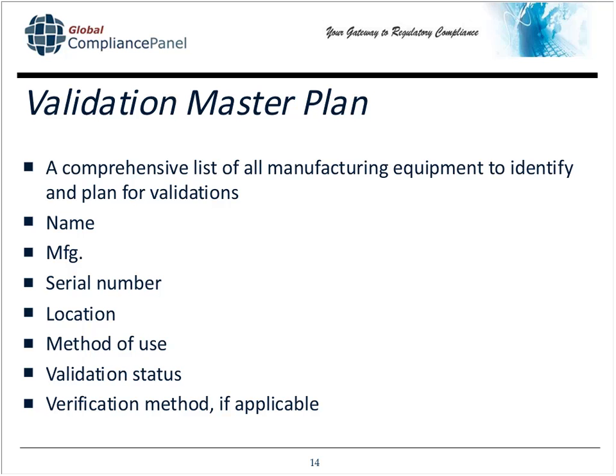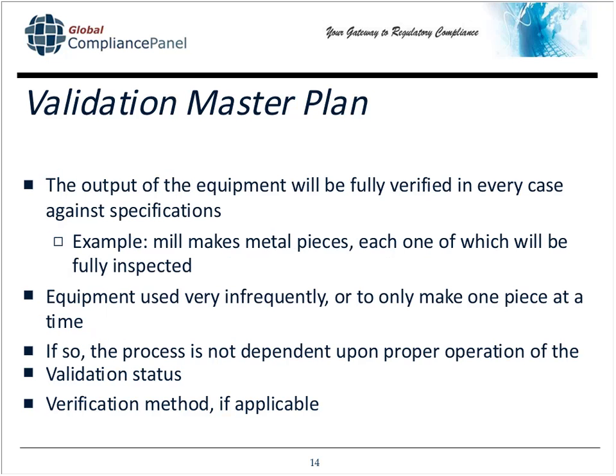In our validation master plan, what we have is a test reference number for the IQ, OQ, and PQ, so we know that a particular piece of equipment has been validated. There is some equipment you have that does not require validation. We'll speak about that in a minute, in which case you're going to verify. So if you verify, you're going to have a verification method, how you verify on an ongoing basis that the output of that particular piece of equipment meets its requirements. Every piece of equipment will have either validation status or verification method.